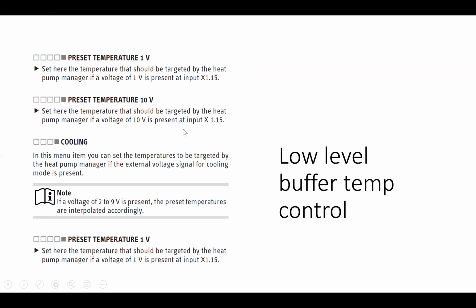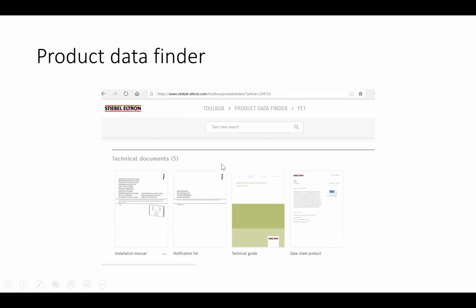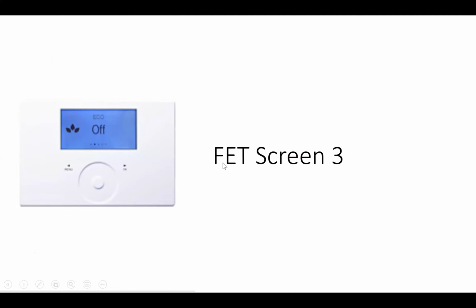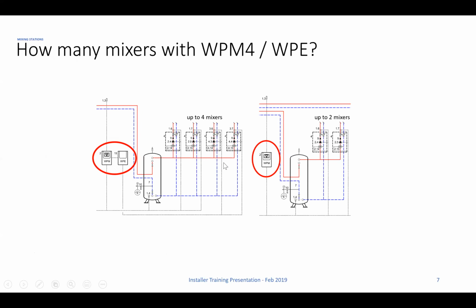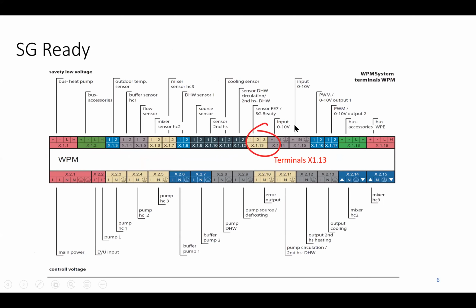Now, for most BMS systems, that should be fairly easy. So, that's what we're getting into here. We're getting into the world of BMS, where we're saying, let's take these two 0 to 10 volt control inputs. We've got an external system. We don't want to use any of your FETs. We don't want to use any of that. We don't even want you controlling any of our pumps. We're going to do all that through our BMS. But we want to tell you what temperature we want that buffer tank, when we want it.